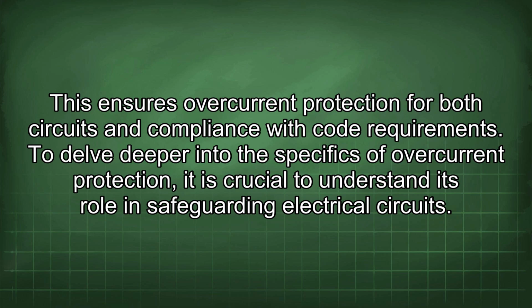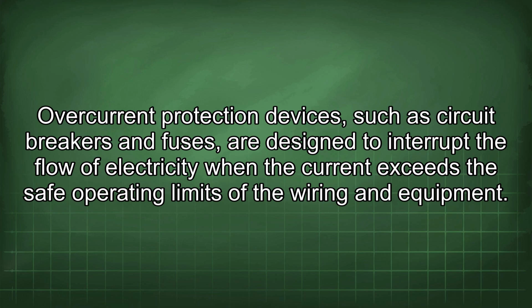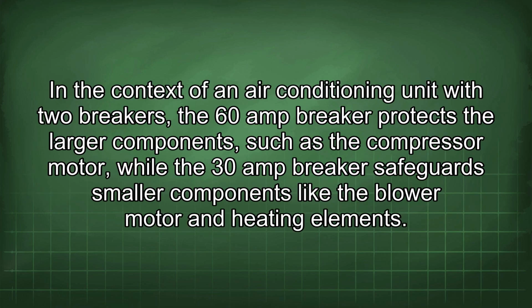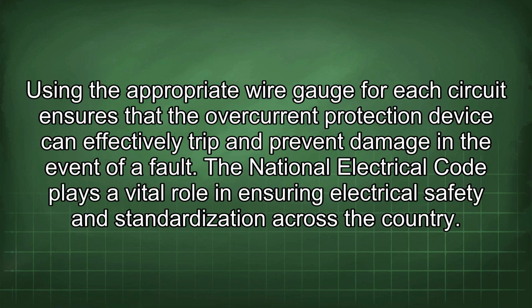To delve deeper into the specifics of overcurrent protection, it is crucial to understand its role in safeguarding electrical circuits. Overcurrent protection devices, such as circuit breakers and fuses, are designed to interrupt the flow of electricity when the current exceeds the safe operating limits of the wiring and equipment. In the context of an air conditioning unit with two breakers, the 60-amp breaker protects the larger components, such as the compressor motor, while the 30-amp breaker safeguards smaller components like the blower motor and heating elements. Using the appropriate wire gauge for each circuit ensures that the overcurrent protection device can effectively trip and prevent damage in the event of a fault.